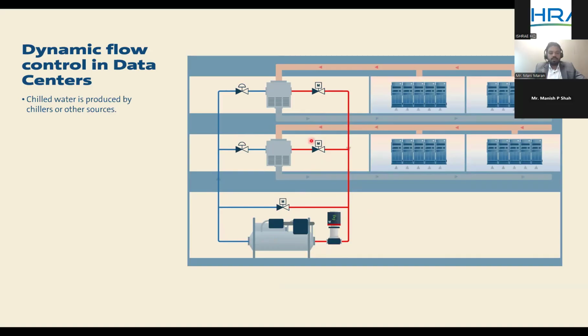Let's say it can be a fan wall unit, or it can be a CRAH unit, or it can be a CDU, cooling distribution unit. The chilled water from the source, from the production loop, is pushed into the distribution loop, which is the secondary side of the system. And if you see, the individual unit has to be balanced with the help of a balancing valve, and further to modulate the flow based on the change in the load on the unit level, we have an actuator based modulating valve which modulates the flow based on the load variation on that particular load. So this is a very typical design that we see today.